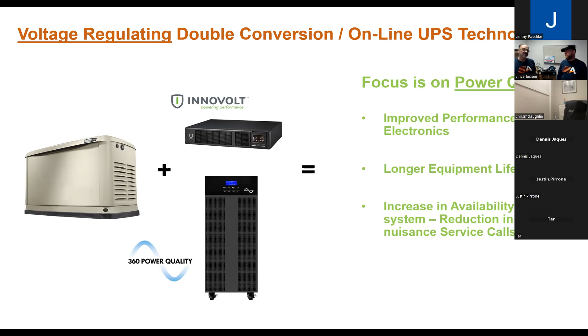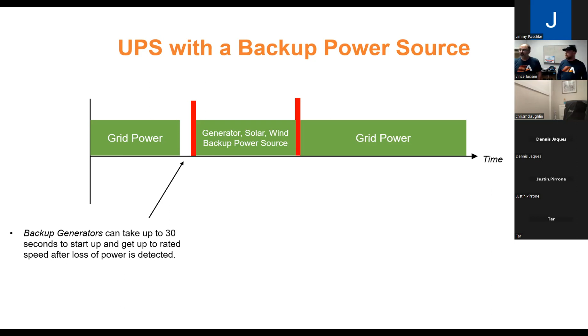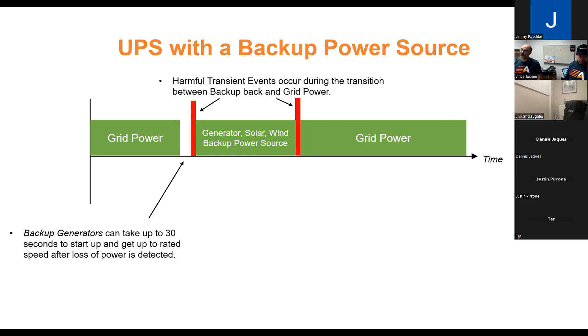If you read this graph, going from left to right is time. You're on grid power, everything's good. Grid power shuts off because a tree falls on the overhead power lines, and you're going to have a power outage, possibly a long one depending on how long it takes your generator to come on. Your generator cranks up, comes up to a certain speed, and then an automatic transfer switch switches over, and you get this horrendous voltage transient, basically a mid-sized voltage surge like you'd get from a lightning strike. It's that severe. Then you're on generator, and when the grid comes back on, the transfer switch switches you back, giving you another big transient.